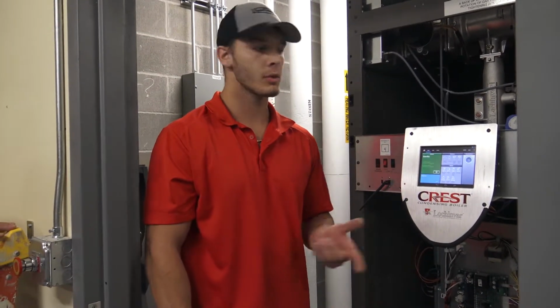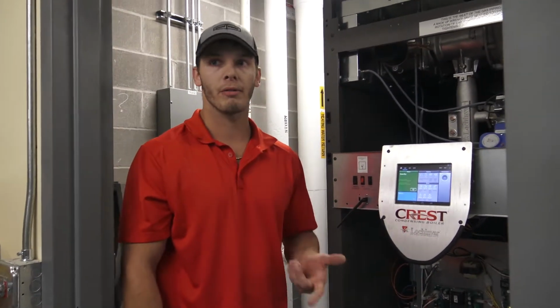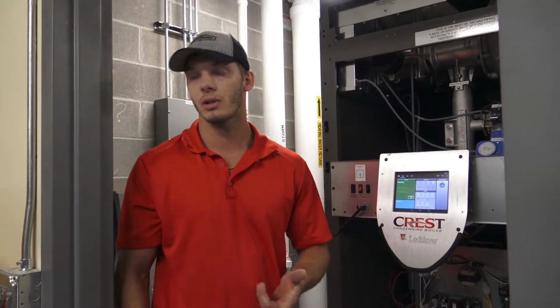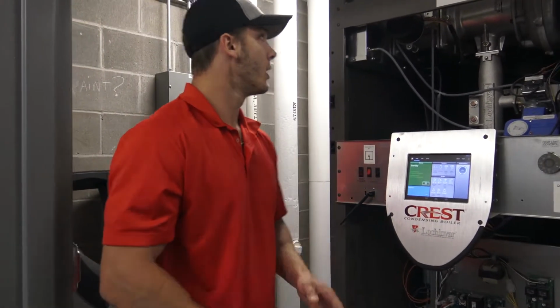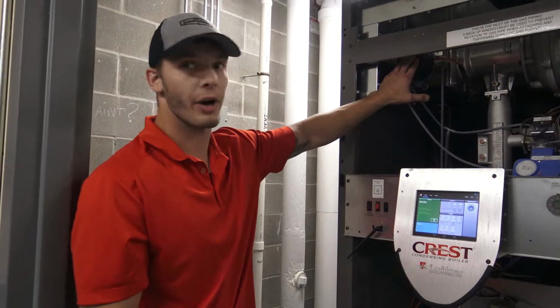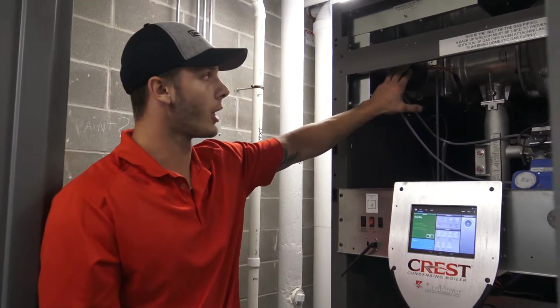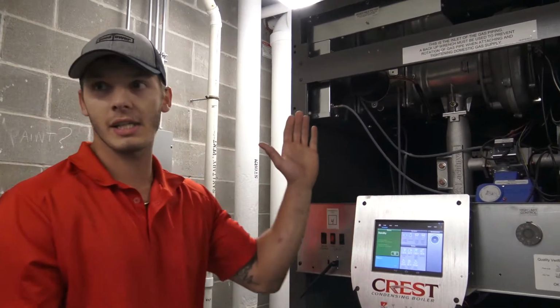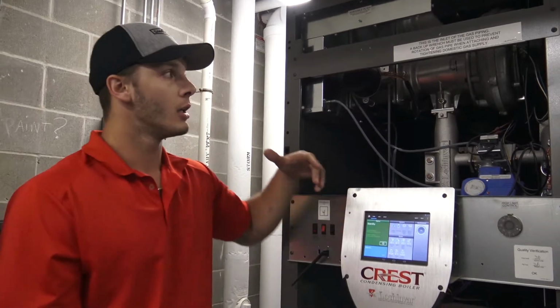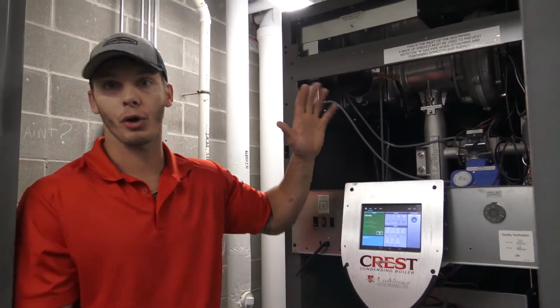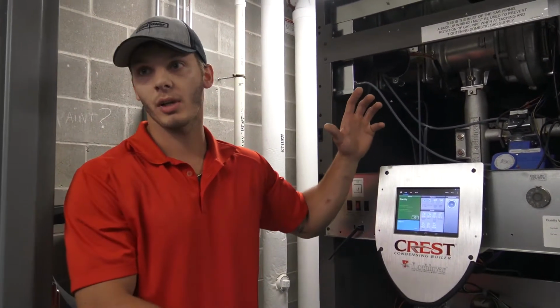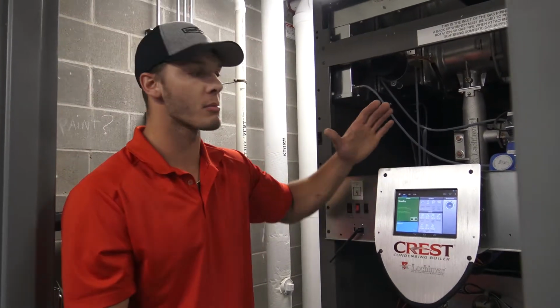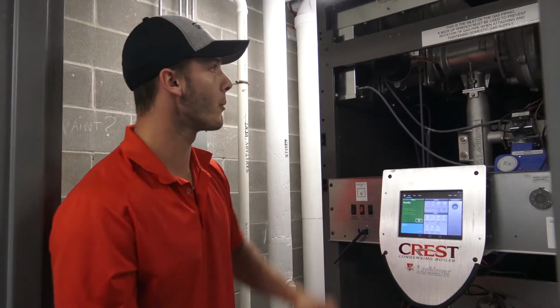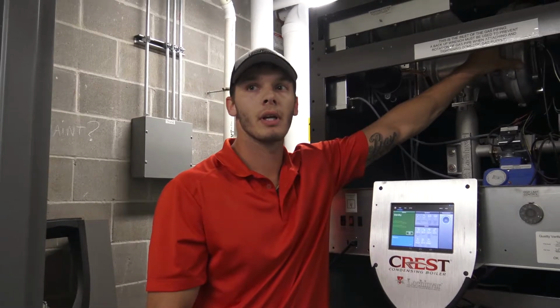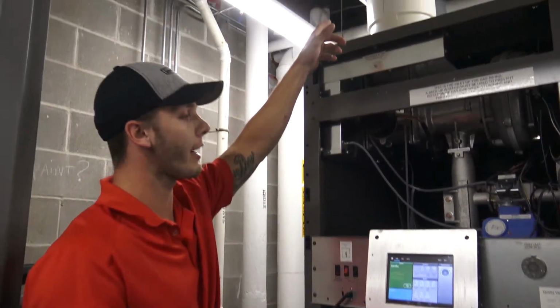It has a 25-to-1 turn down ratio. So at minimum you can fire at 70,000 BTUs. This right here is our air damper valve. Just pretty much opens and closes as the boiler turns on and off. On low fire it'll be closed so you don't get a gust of wind blowing out a small flame, and then as high fire comes it'll open up.